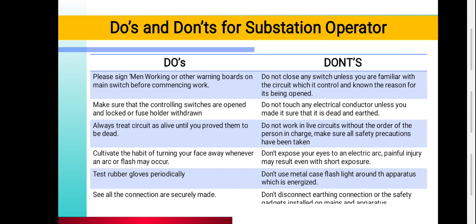Always ensure that whatever you touch is either switched off or properly earthed, because even with proper earthing, aging or connection problems in the earthing can still cause a shock. Therefore, always treat every circuit as live until you prove it to be dead. Never work on any live circuit unless you have authorization from a competent person and have taken all proper safety precautions.